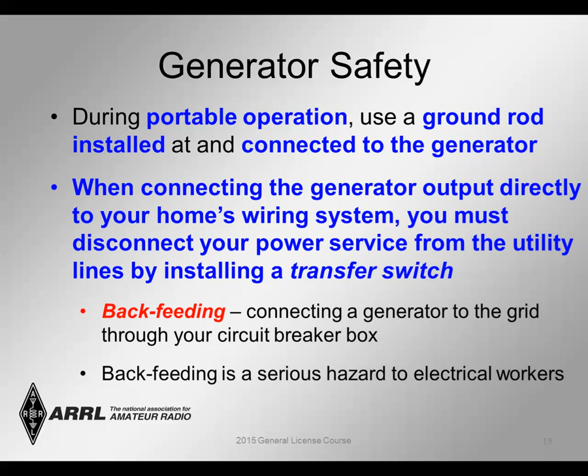Since then, I've installed a generator that has a transfer switch, and that way it's all automatic. The generator is constantly monitoring the AC power coming into the house. If it detects a loss of power for a set time, then it'll start the generator. It'll disconnect the main breaker, essentially disconnecting the house from the grid. And then once it's done that, it'll connect the generator to the house circuit. So it's all done automatically, and then it'll repeat that sequence when the AC power comes back on the grid. So that's the better way to do it if you're going to use a generator for your house.